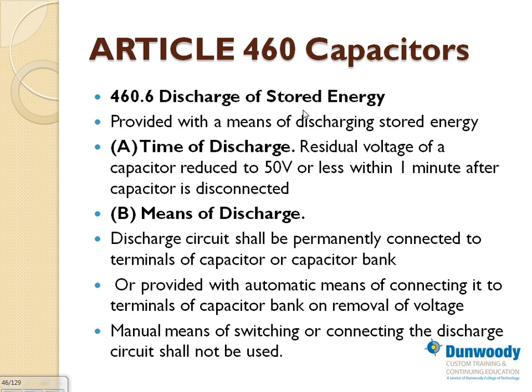The discharge shall be permanently connected to the terminals of the capacitor or the capacitor bank, or provided with an automatic means of connecting it to the terminals of the capacitor bank on removal of the voltage. You remove the voltage, and it should connect the capacitor to a bank of resistors that burns off this energy. Also, manual means of switching or connecting the discharge shall not be used. I'm sure you guys are probably grandfathered. With the new capacitors, when you de-energize the capacitor, the action connects it to a bank of resistors and burns the energy right through it, so it doesn't zap you. Any comments, any questions about that, when it comes to capacitors?